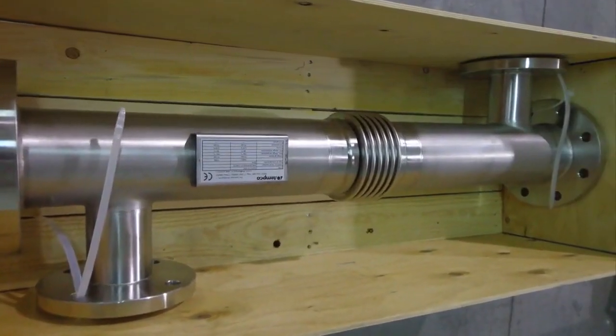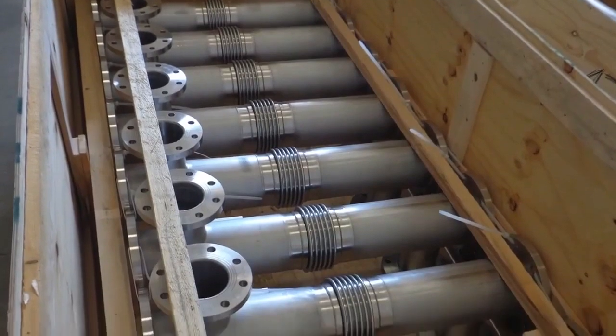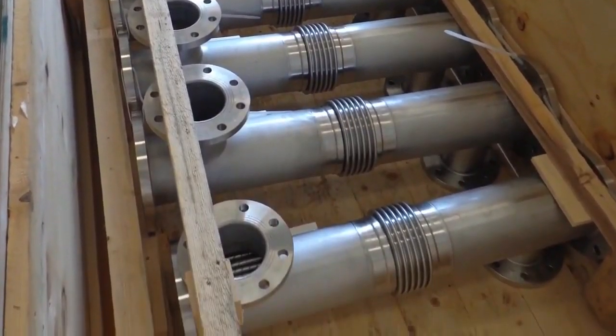Moreover, the exhaust fumes reach high temperatures, typically ranging from 600 to 650 degrees Celsius, making it imperative to utilize a tubular bundle heat exchanger for this purpose. They are very specific exchangers, typically with tubular bundles with straight brushable tubes. Why? Because even though the fumes are clean, they always contain a small amount of combustion dust, a small amount of combustion particles, and therefore they need to be cleaned from time to time. So they are designed with straight brushable pipes, an outer shell, and are usually made of stainless steel.